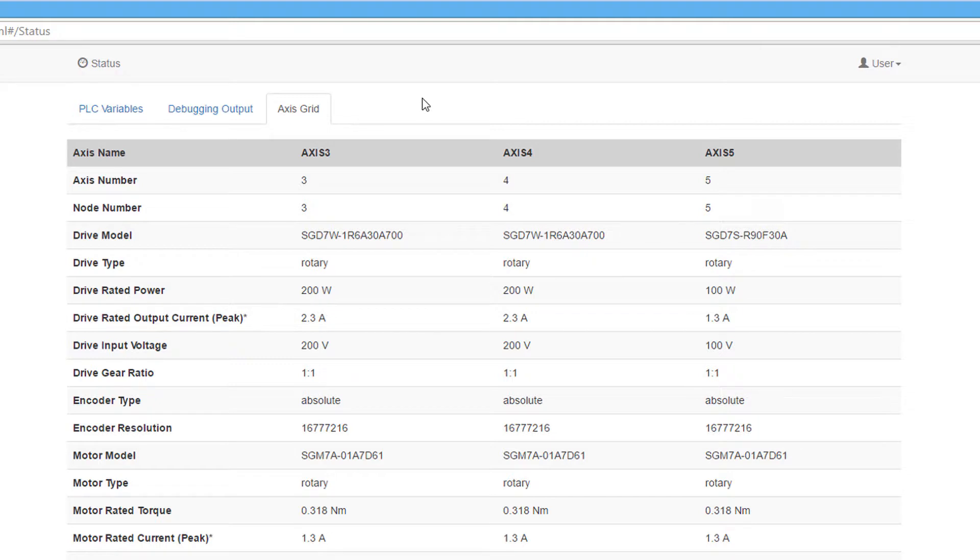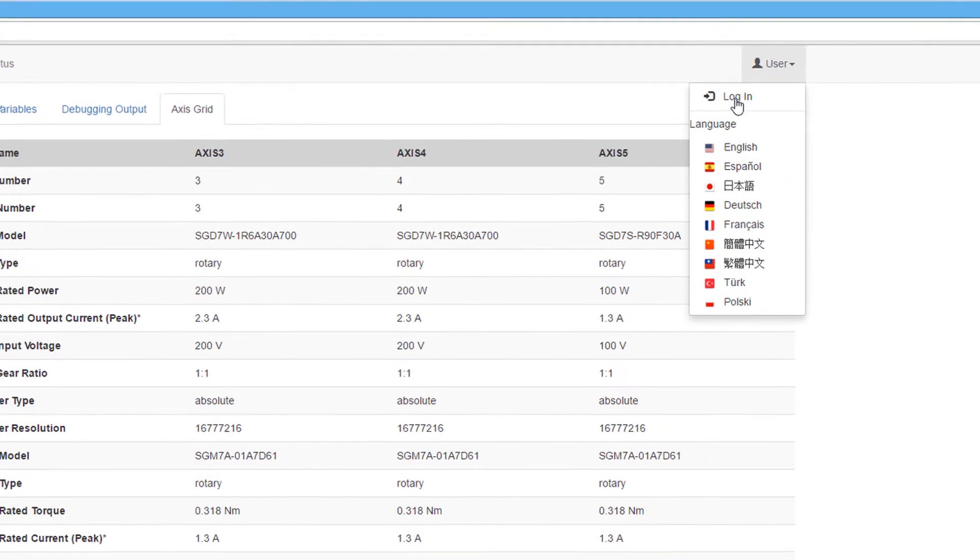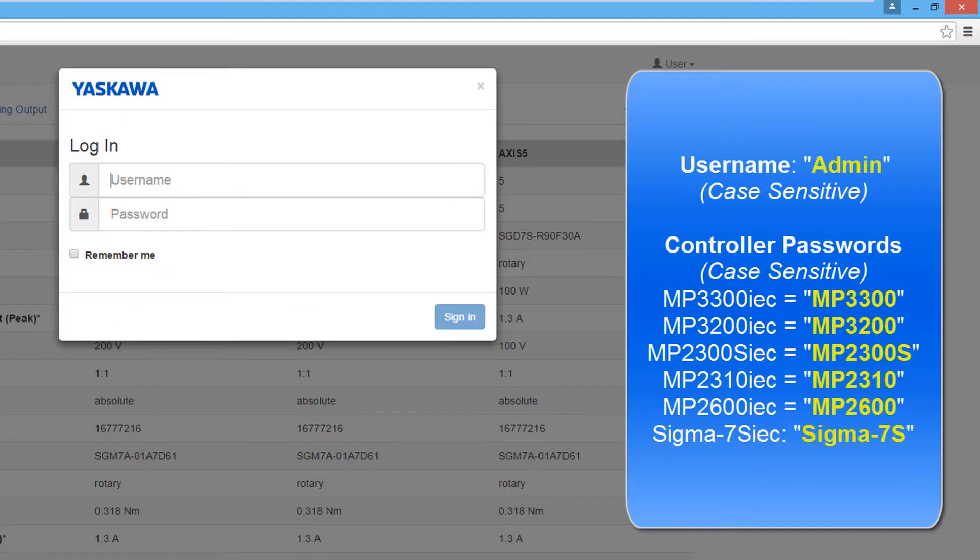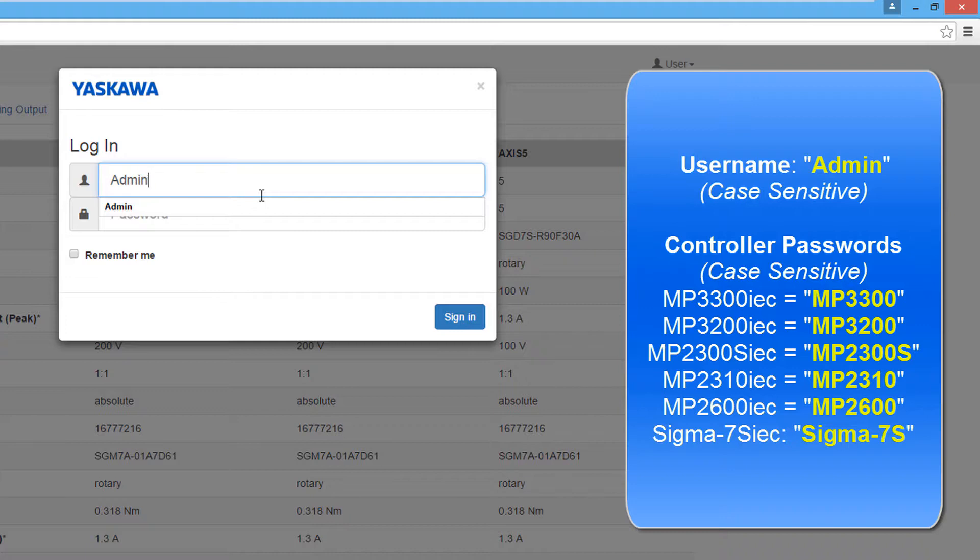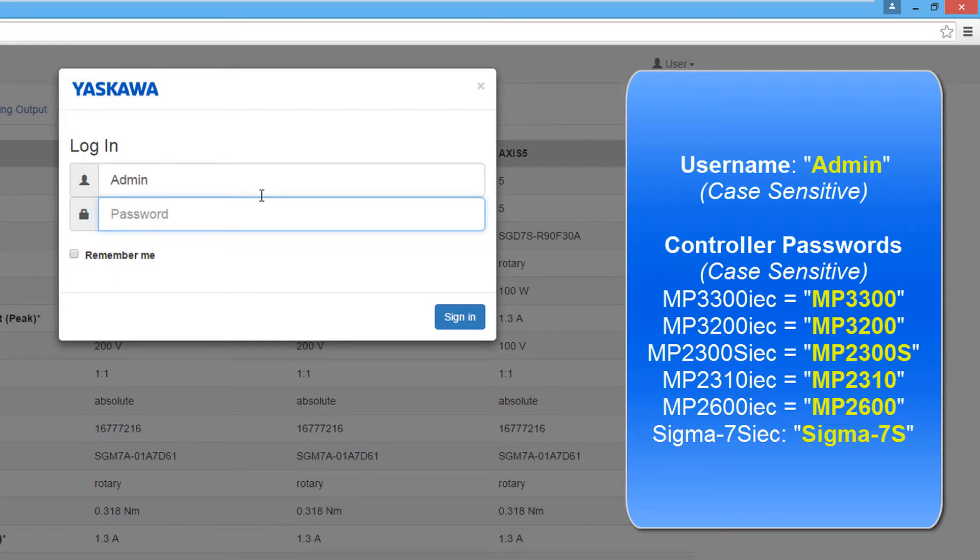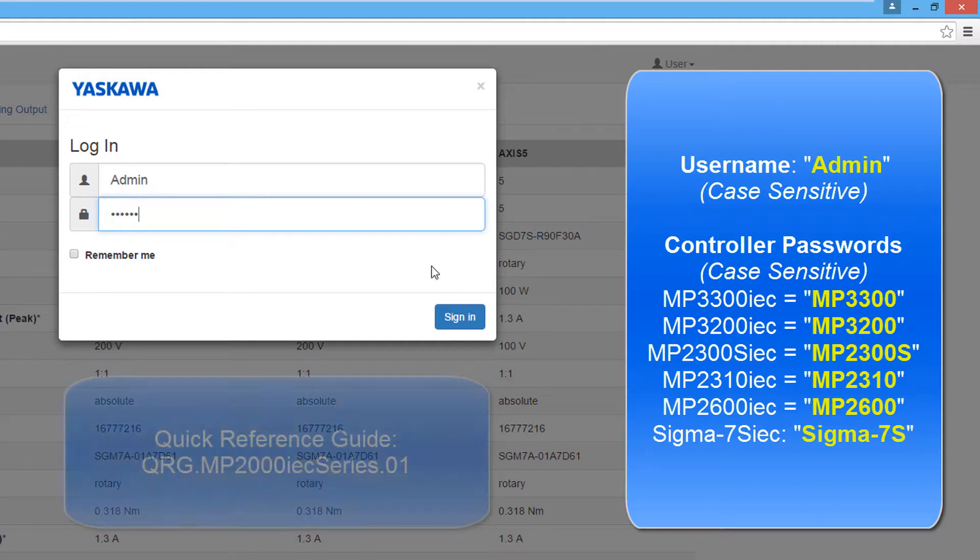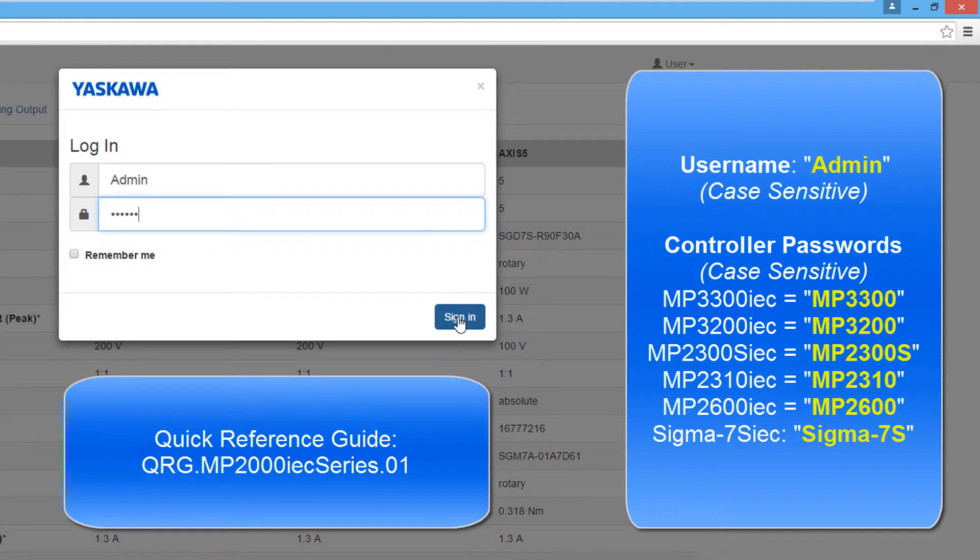To see more information, you need to log in. The user menu allows language selection and log in. The username for all of the motion controllers is ADMIN, with a capital A. The password depends on which controller is being connected to. In this case, I am connecting to an MP3300 IEC controller, so the password is MP3300 in all caps. The passwords for the other controllers follow the same format and can be found in the quick reference guide.